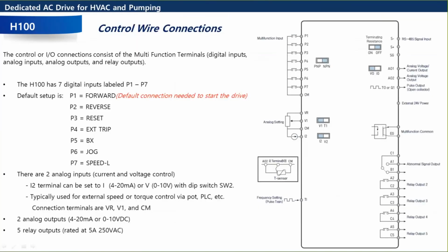So here's just the control wire terminals, and the reason why I'm showing this, it might be overly technical for some of you guys, but a lot of the functions we're going to be talking about are directly related to inputs and outputs. So you could close outputs at certain times or certain speeds. You could have an input close to tell the drive to do something. So we just figured it'd be good to mention it. So we're talking about the I/O.